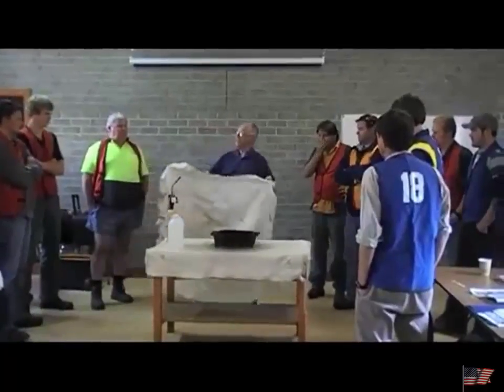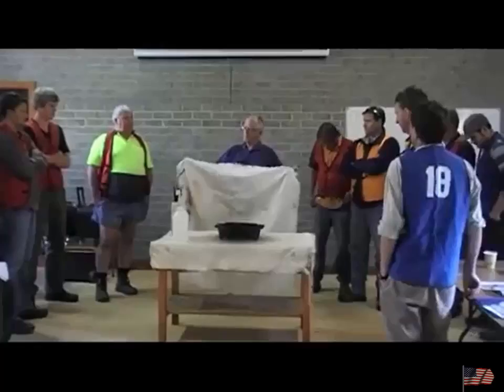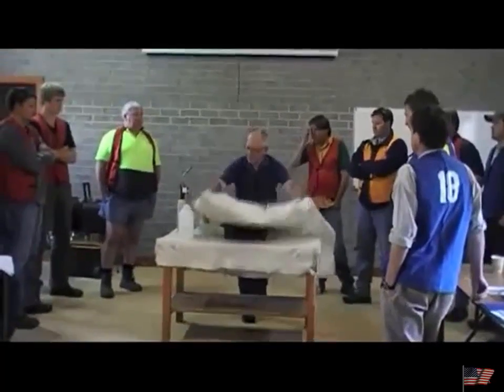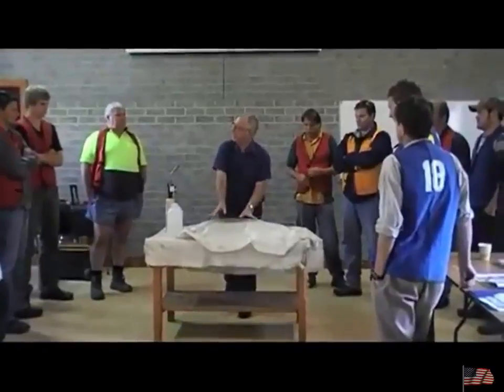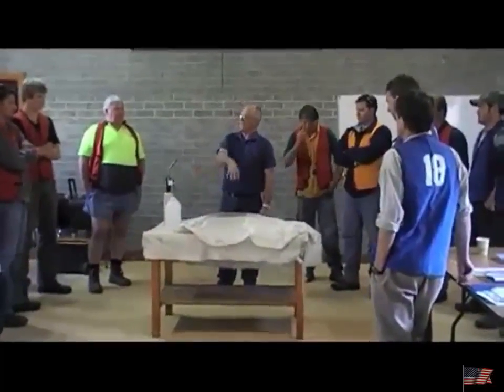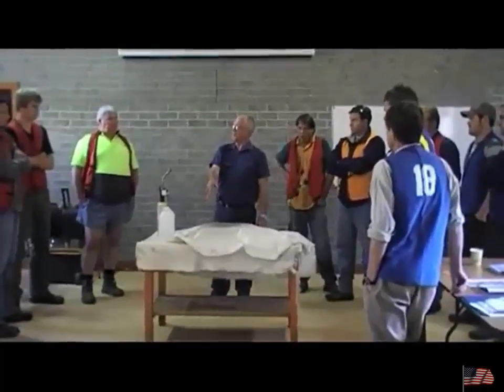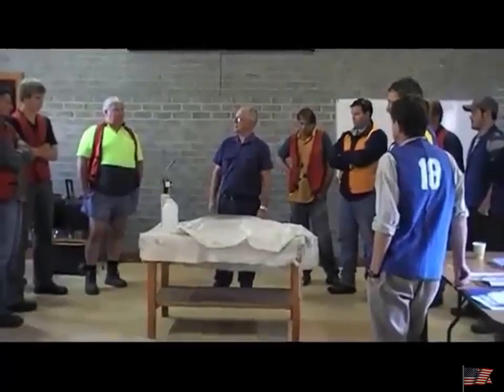They're normally a one-use only piece of equipment. But the thing is, when you put it on a fat fire, if the fat gets impregnated onto the blanket, the next time you go to use it, the blanket will catch on fire. Other than that, they won't catch on fire at all. They're made of a woven fiberglass type material that doesn't burn. Okay?